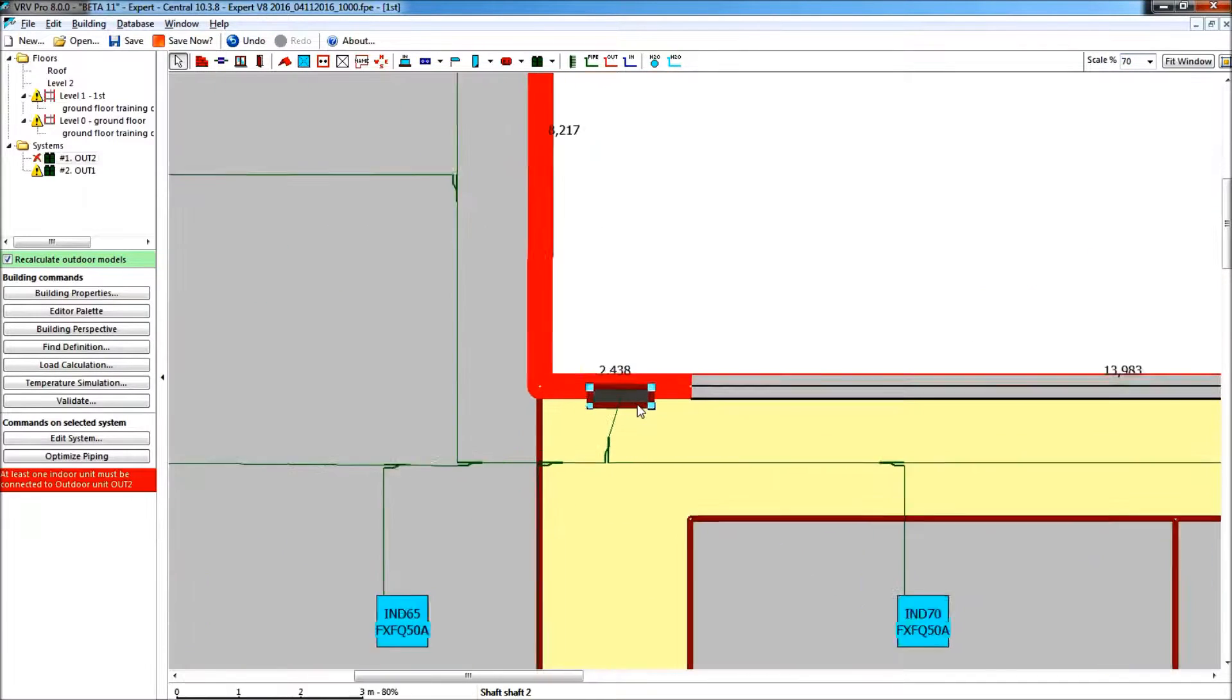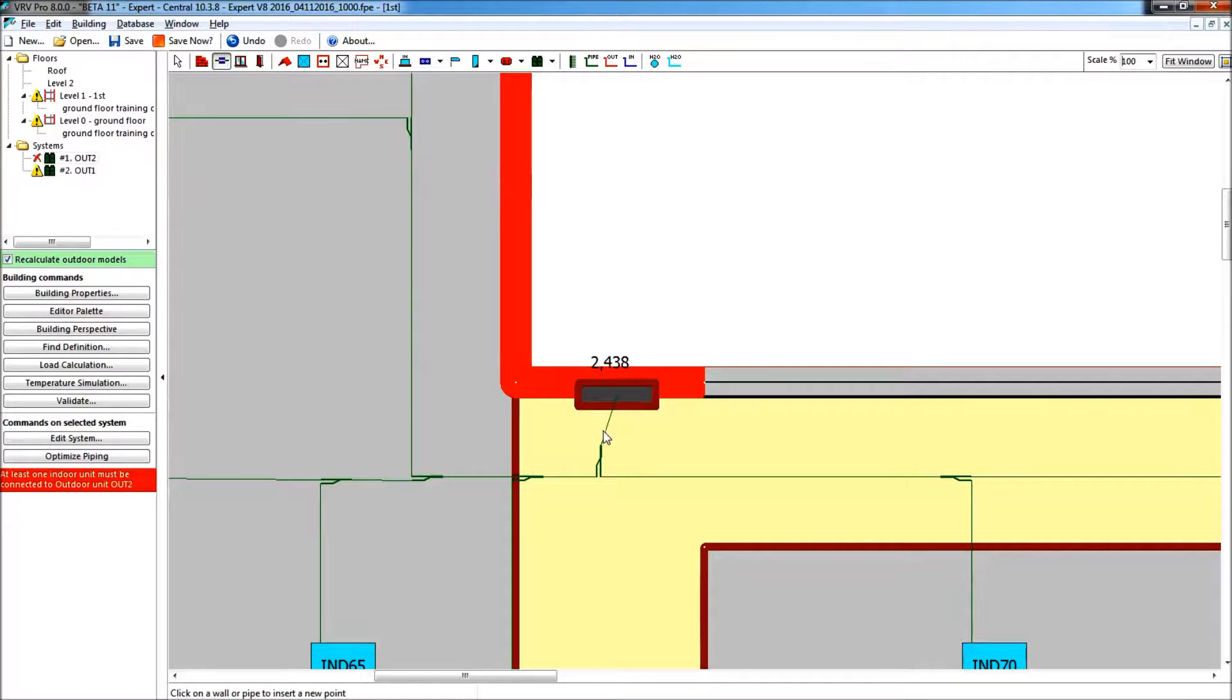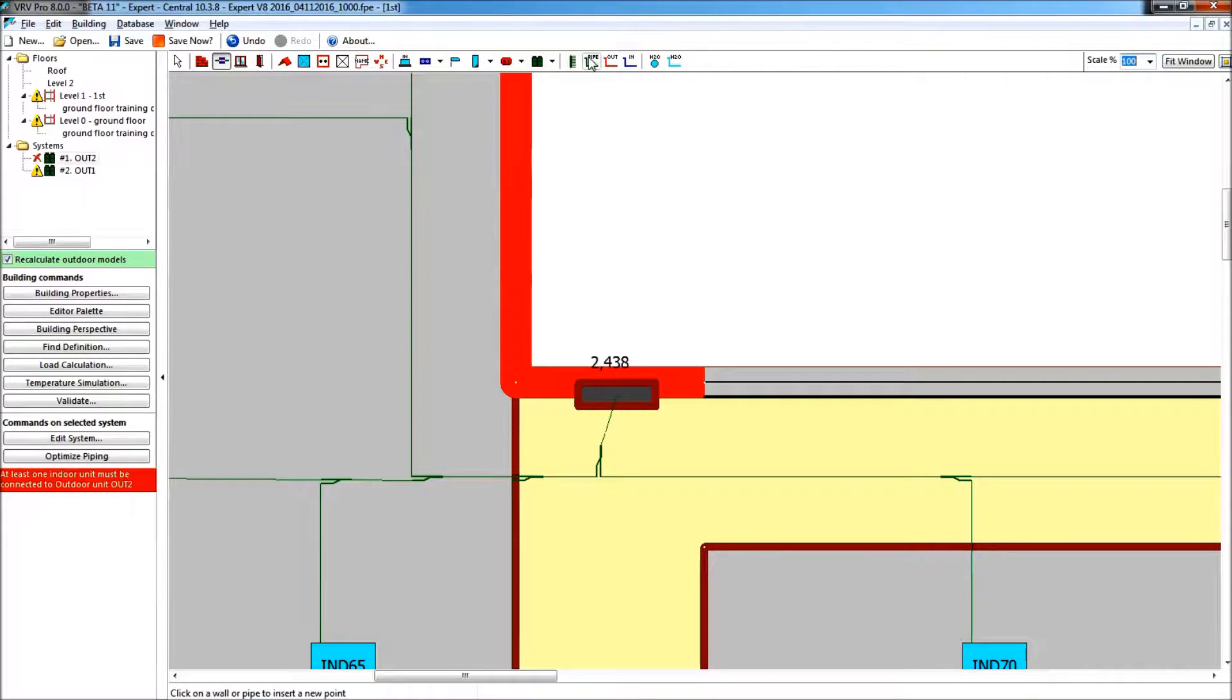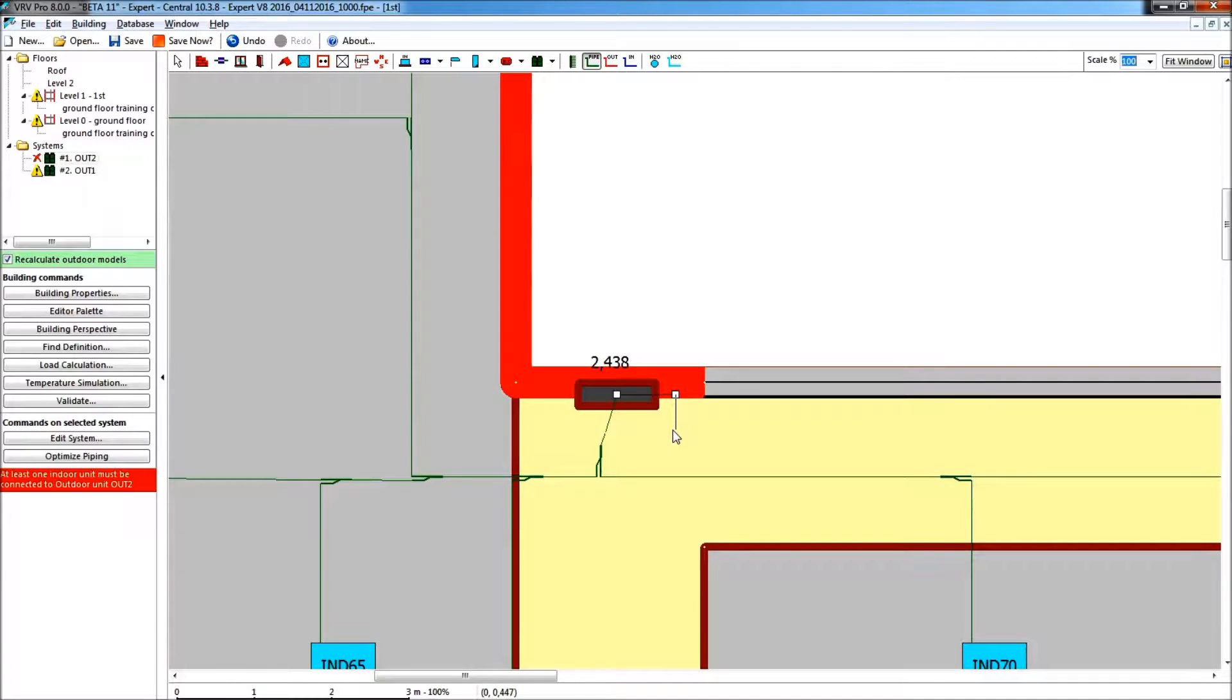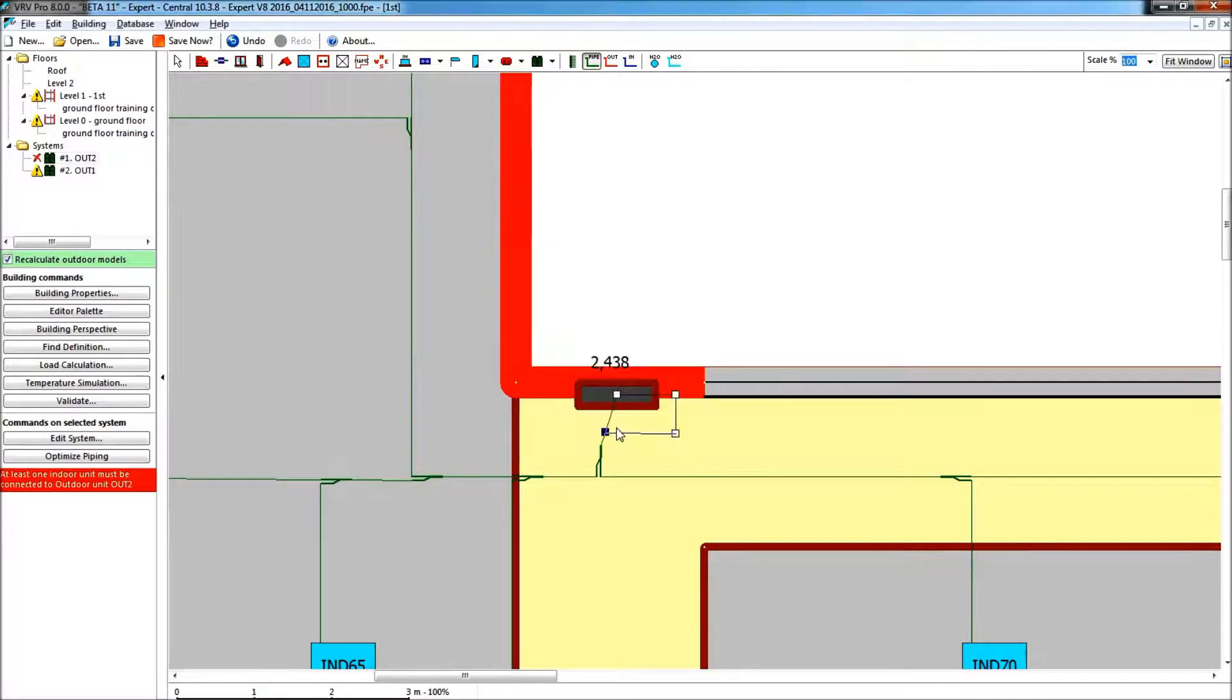So from this joint I go into the shaft. Let's have a closer look on what's happening to that shaft. So the first thing I have to do is to insert the point where I will connect a new joint that will link both the ground floor and that first floor. This will be here. Now that I have this point, I can take my piping, take it out of the shaft, go down and link it to that joint over here. So, obviously this is coming from joint zero, from the ground floor, and I confirm.